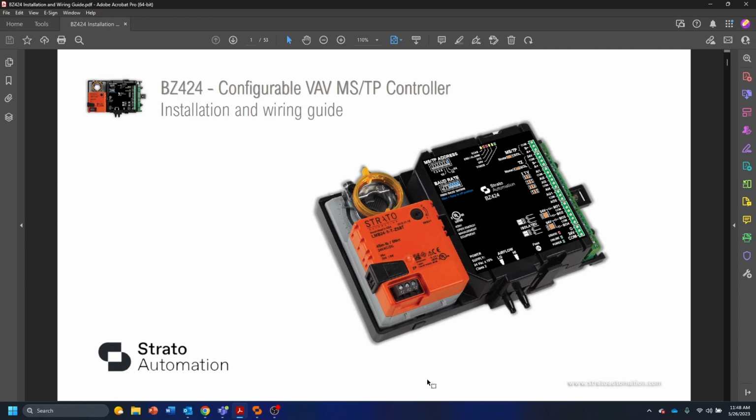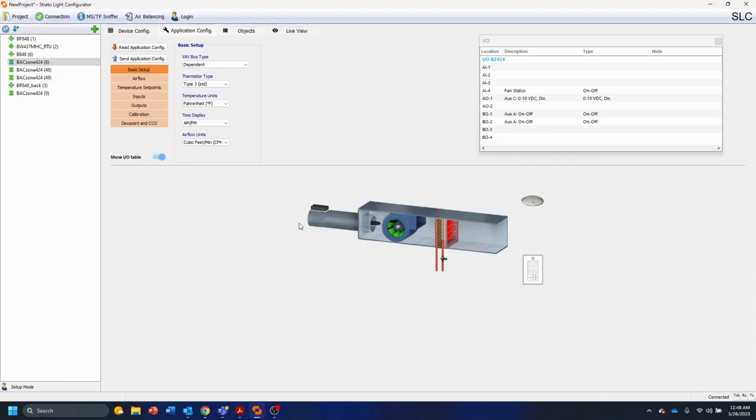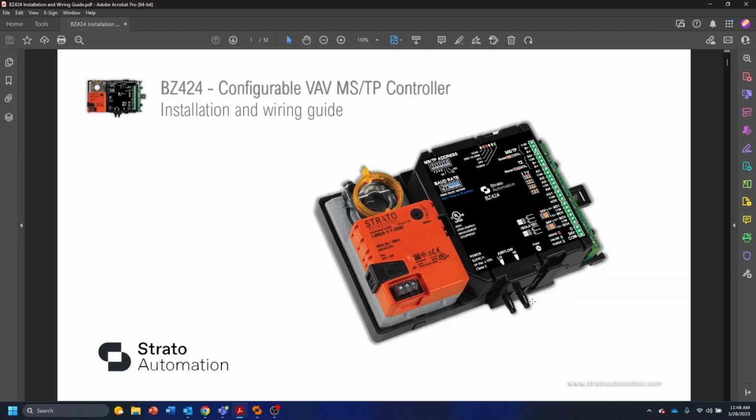High side matches the high side of your box or your flow meter, and the low side matches the low. On our controllers currently, the airflow meter is not bidirectional, so you have to hook it up the correct way. That's one spot where I sometimes see people have issues. They have their lines backwards, and they just need to flip them, and then they start getting proper control from their controller.